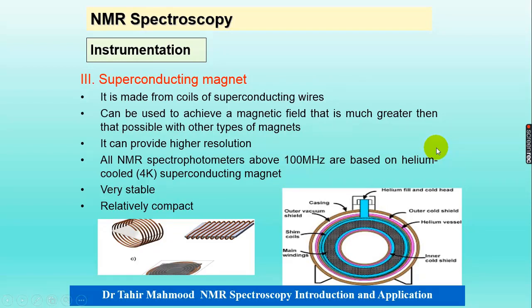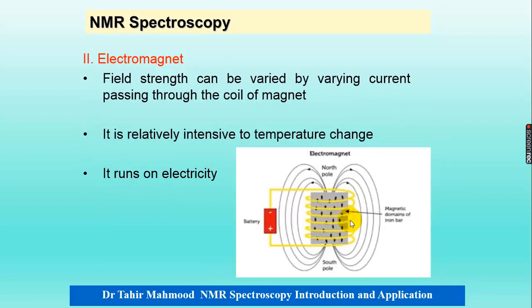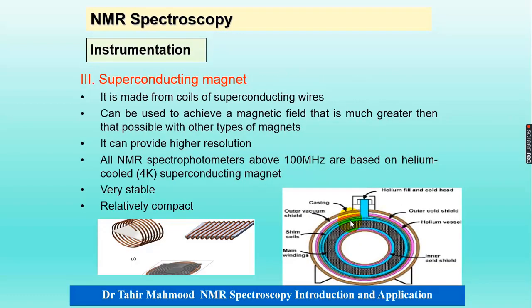The third type is the superconducting magnet, which is mostly used in all types of NMR spectrometers. It is made of coils of superconducting wires as shown in the diagram, and can achieve a magnetic field much greater than other types. It provides higher resolution. All NMR spectrometers above 100 MHz are based on helium-cooled superconducting magnets. It is very stable and relatively compact.